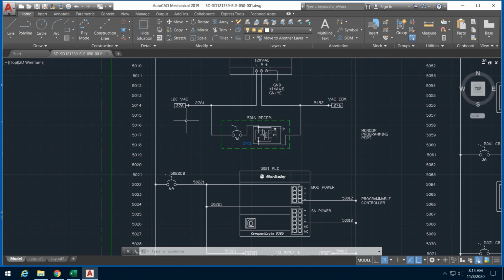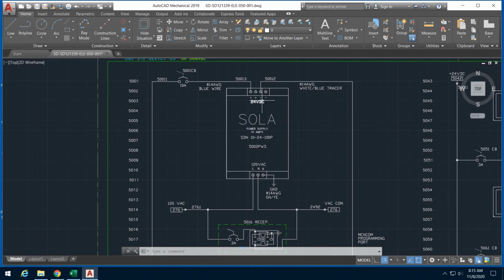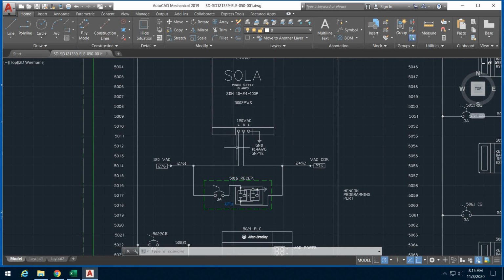If I were to go to sheet 2, line 76, I'd probably find a transformer or something, or possibly a circuit breaker that's supplying power, because you see there's no circuit breaker before the power supply. So probably there's 120 going through a circuit breaker that ends up coming out to here. And you can see that it is wire number 2761, going in. And the neutral is from sheet 2, line 76, and the wire number is 2490. So most likely, sheet 2, line 49 has a transformer on it, and wire number 2 on the transformer is the common for the AC system. You can see right here, there's the common.